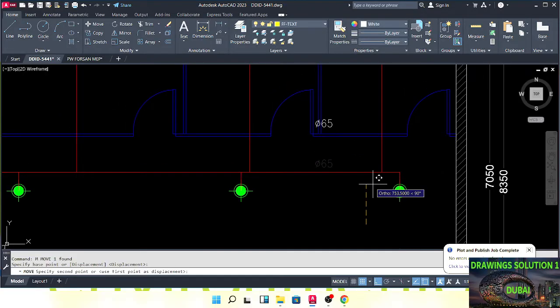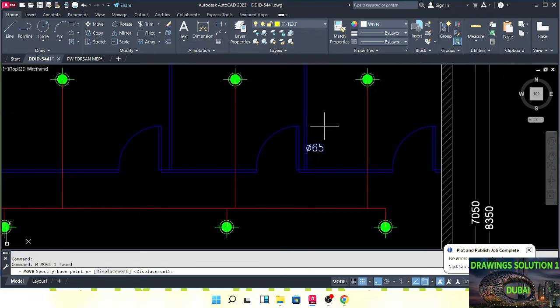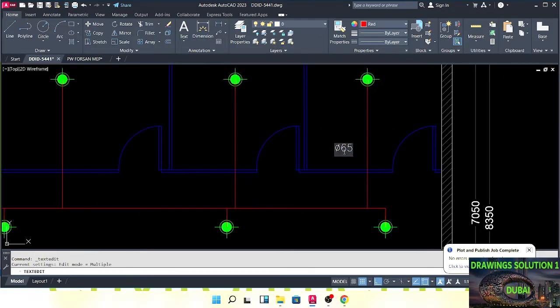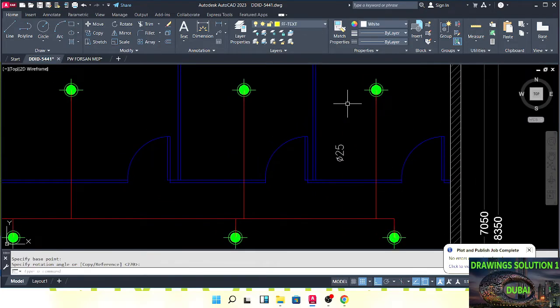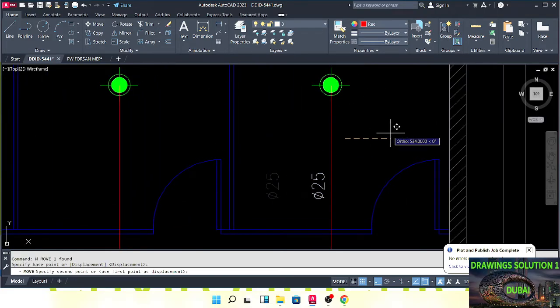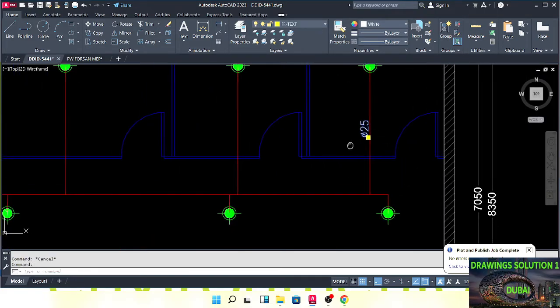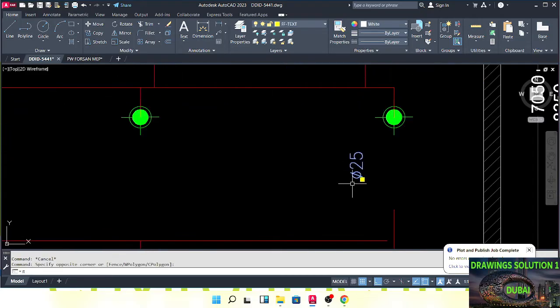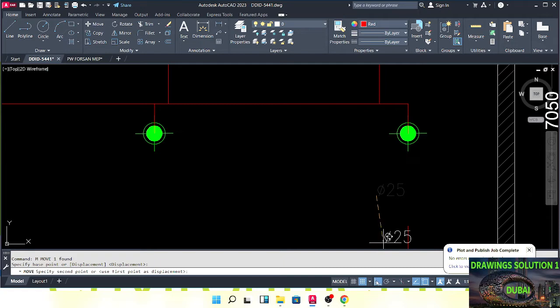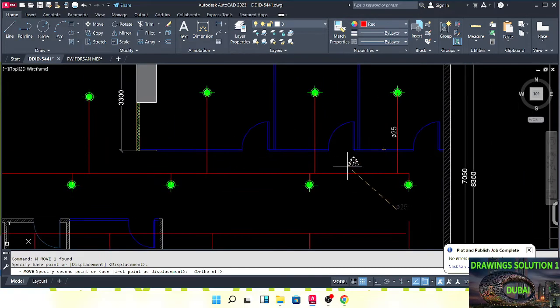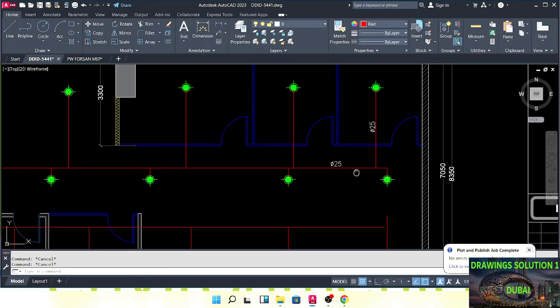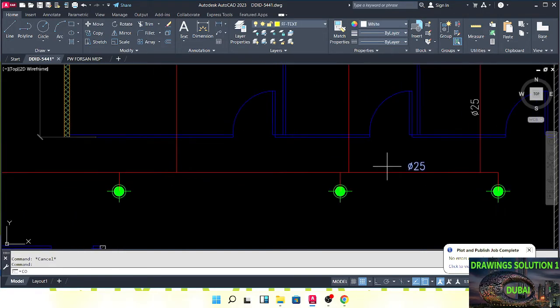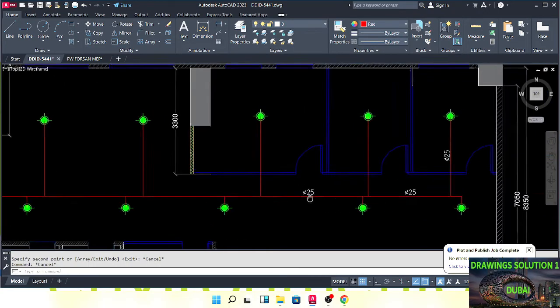Just connect with this one. If you have three sprinklers the pipe size should be 32mm. If we have one sprinkler the pipe size should be 25mm dia. If we have two sprinklers with this pipe we can also use 25mm dia.